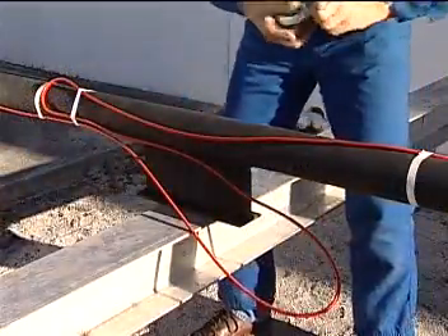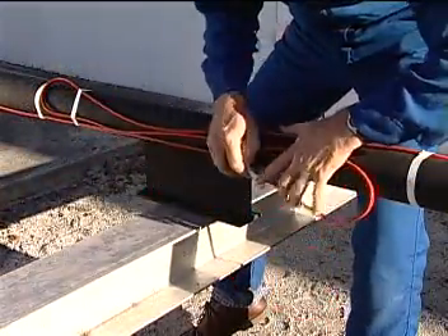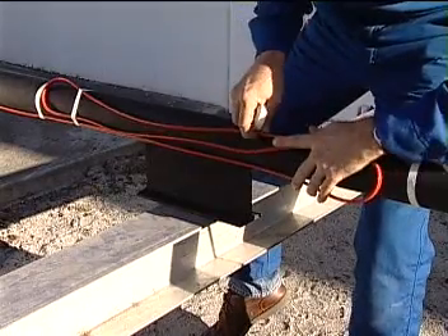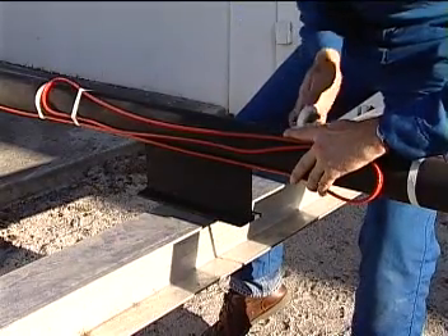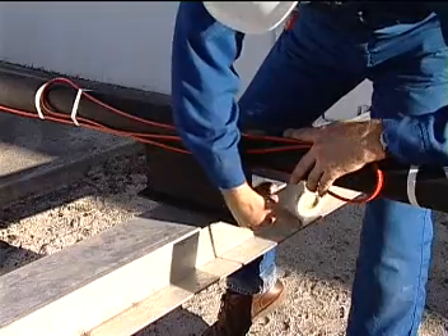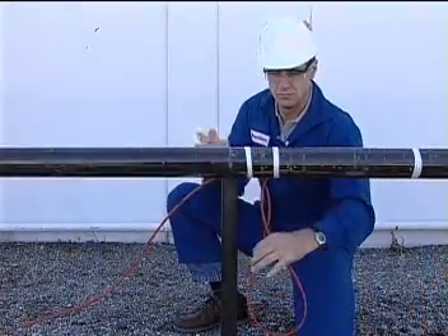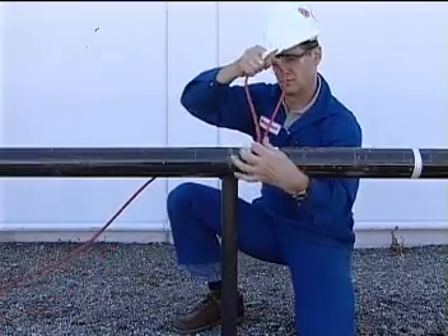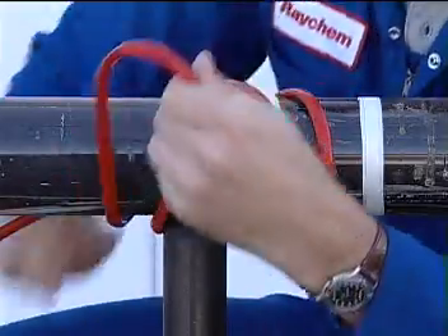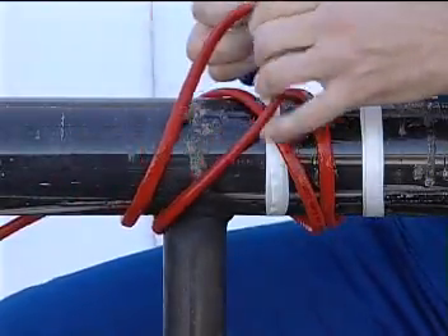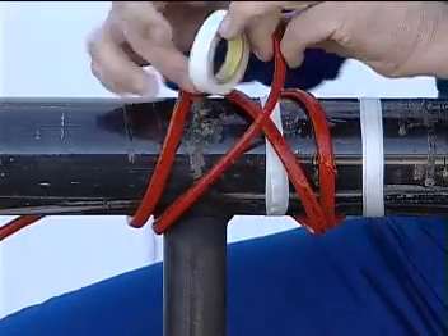For example, this additional cable has been pulled back to about 3 times the length of this support shoe. This is enough to form these 2 loops, which are then each secured with tape. When you encounter a welded column support like this, first form a large loop secured by tape on the side of the support. Then, wrap the cable around the pipe, covering as much of the pipe as possible next to the support.